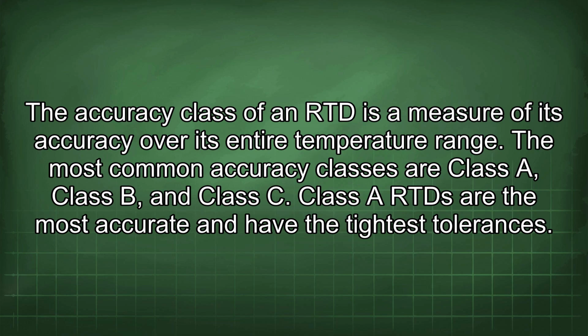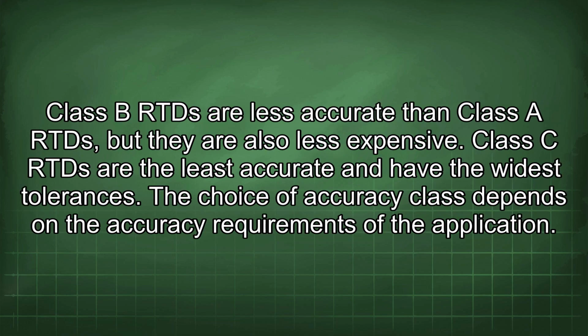The most common accuracy classes are Class A, Class B, and Class C. Class A RTD are the most accurate and have the tightest tolerances. Class B RTD are less accurate than Class A RTD, but they are also less expensive. Class C RTD are the least accurate and have the widest tolerances. The choice of accuracy class depends on the accuracy requirements of the application.